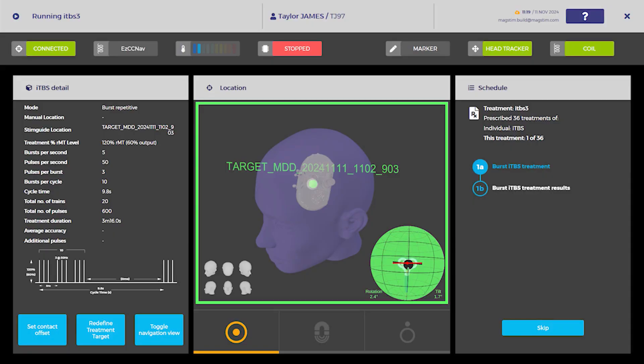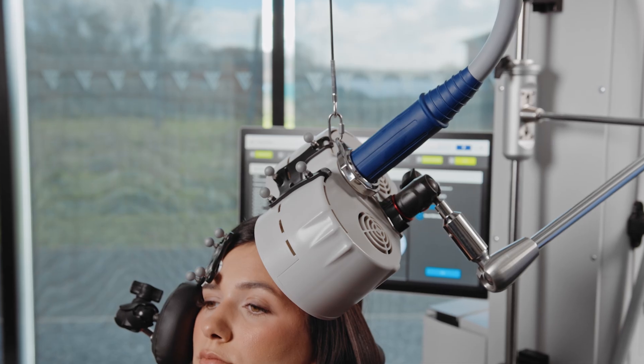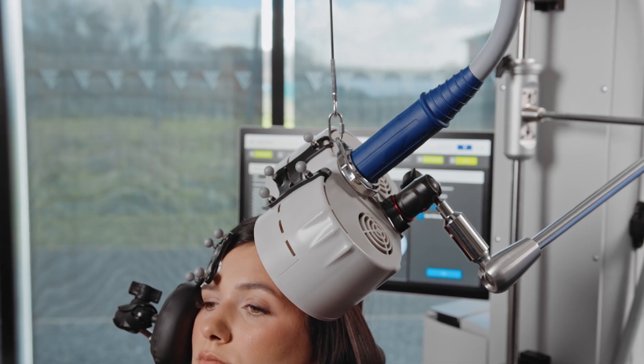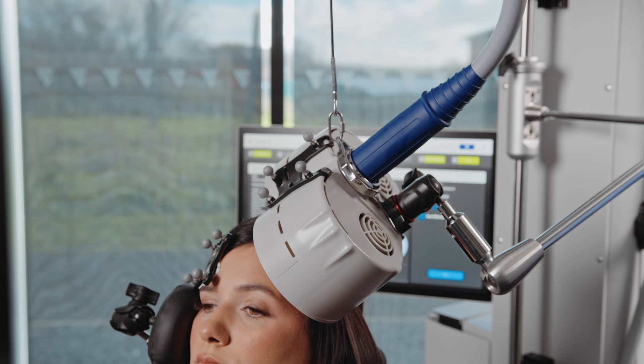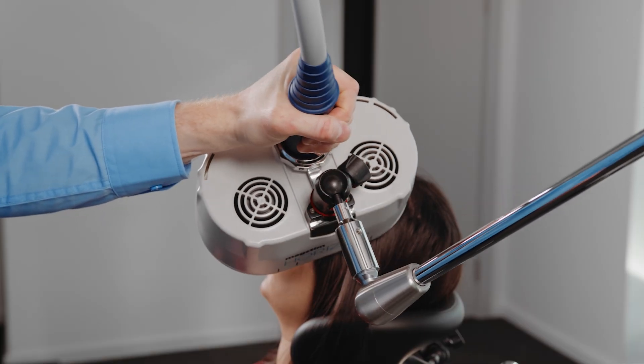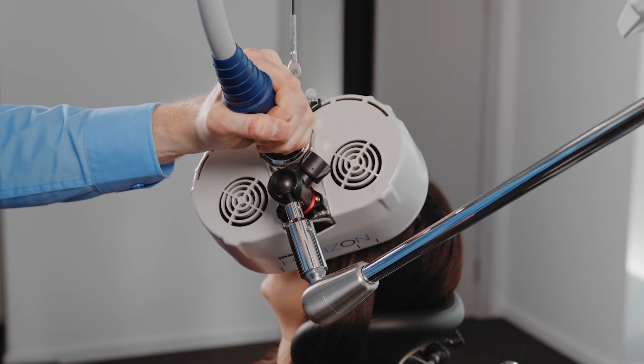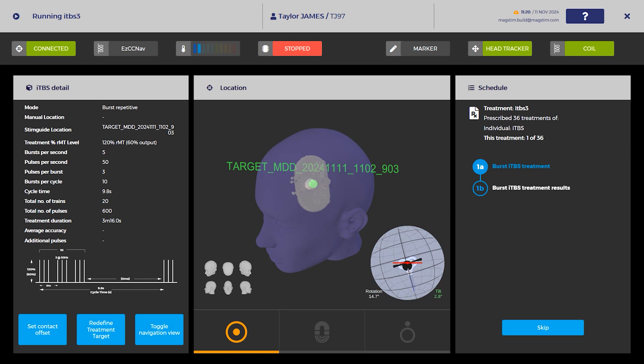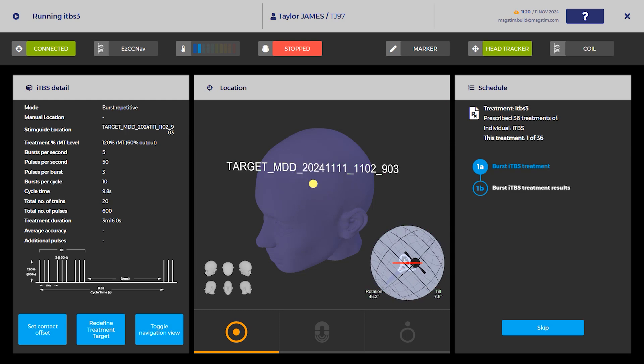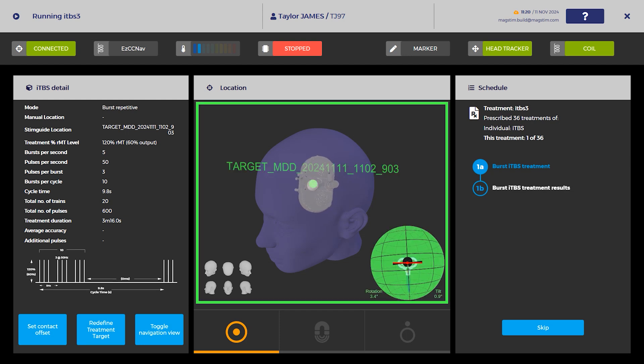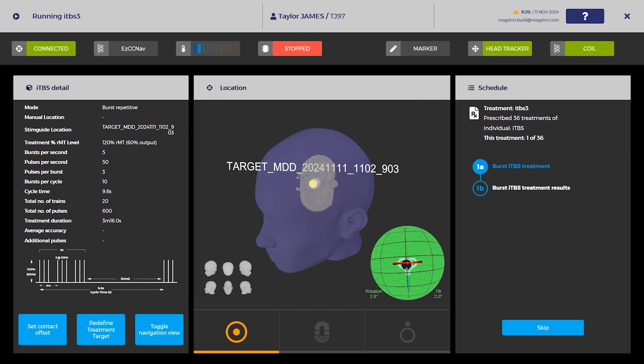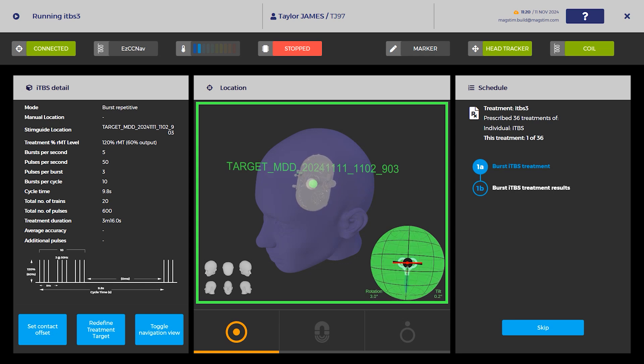Ensure that the treatment location, gimbal, and border all turn green. Visually confirm the coil is in contact with the head. The gimbal is used to manipulate the coil into the correct orientation. The goal is to get the red dot into the center of the black circle and the red lines in the middle of the two black triangles. The line and triangles represent the left and right rotation. The black circle represents the forward and backwards tilt and the left and right side tilt.